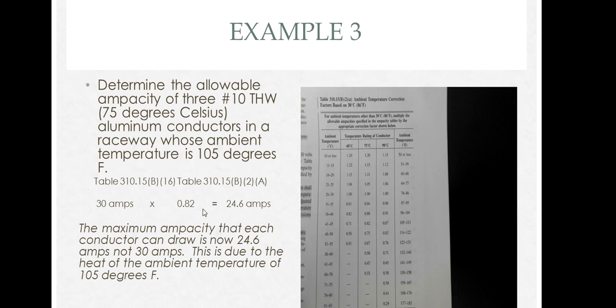We simply multiply that 0.82 factor to 30 amps. Now our conductors can only carry 24.6 amps. This is due to the increase in temperature of the raceway.